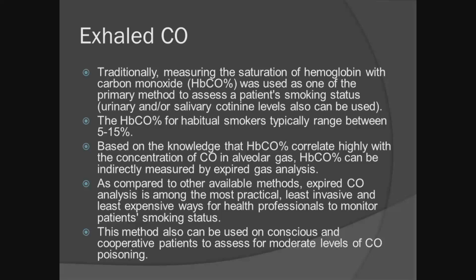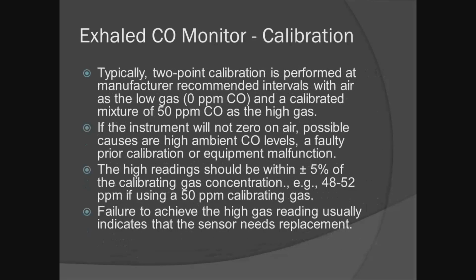In theory, it could be used for carbon monoxide poisoning, but it's typically not what we end up doing. Calibration is done with we expose it to air where there is no carbon monoxide, so it's 0 parts per million. Then we use a calibrated gas of 50 parts per million as the high point. And if we have problems with calibration, it could be either that there was a bad calibration or the equipment's malfunctioning. And what we're looking for is readings on the high end within 5% of that 50 parts per million.